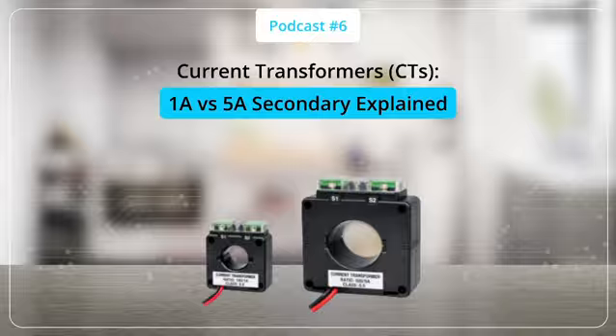For high-load applications, 5A CTs are often preferred due to their higher burden capacity. It is also important to follow system requirements and applicable standards. If you are planning future expansion, choosing a 1A CT can offer more flexibility. In many cases, consulting an expert and evaluating system requirements carefully can help ensure the right decision.